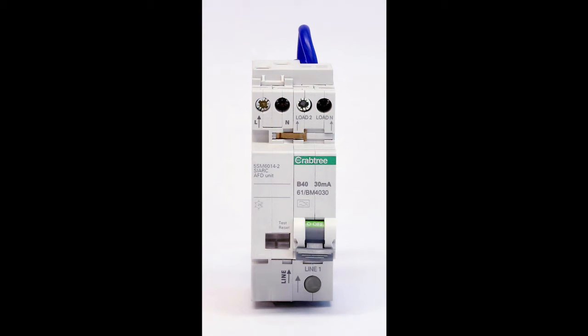Health and safety. Regulation 462.1.201 requires a means of isolation, a main linked switch or circuit breaker, at the origin of every installation and in situations where this will be operated by ordinary persons, for example on a consumer unit in a domestic household. The main switch must interrupt both live conductors, live and neutral, of a single phase supply. Starbreaker Mini RCBOs and AFDDs provide this same safety protocol to individual circuits too, because they include switched neutral as standard.